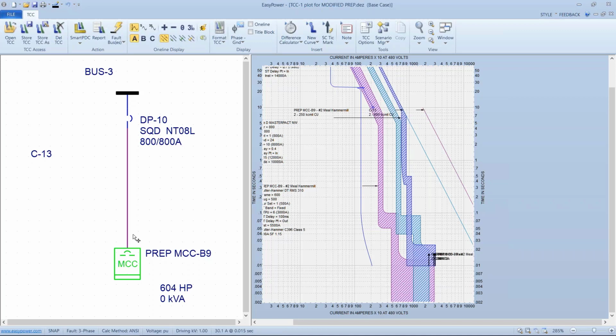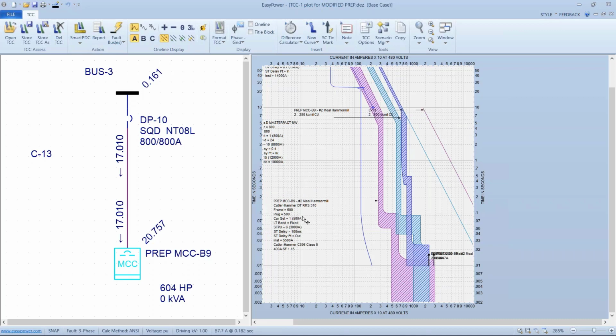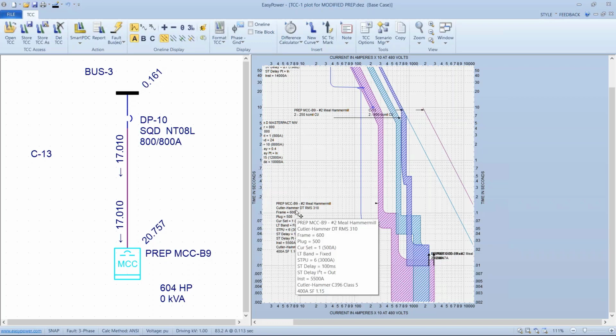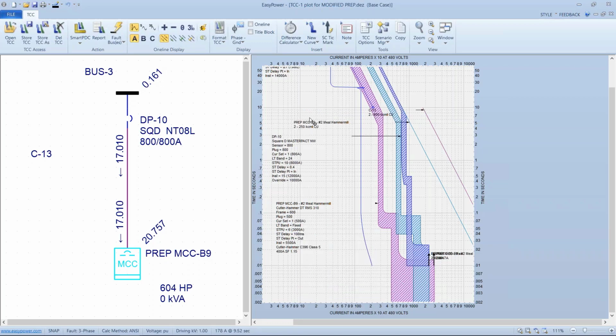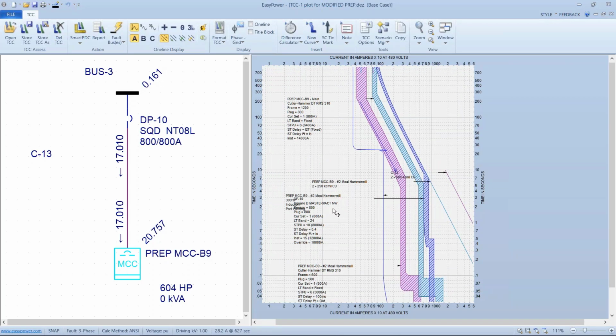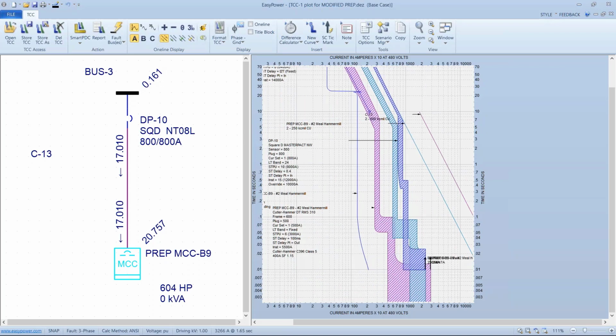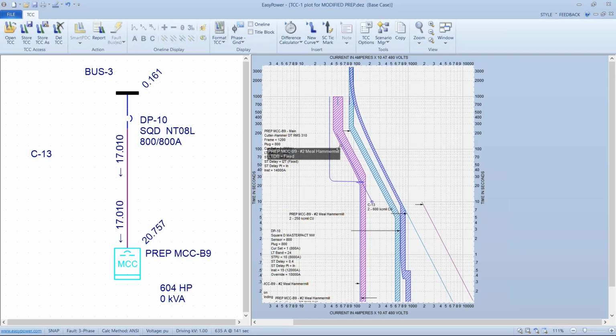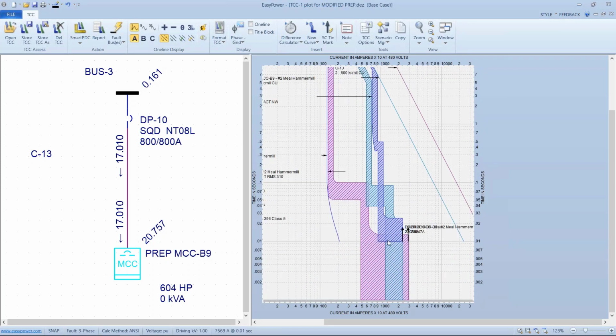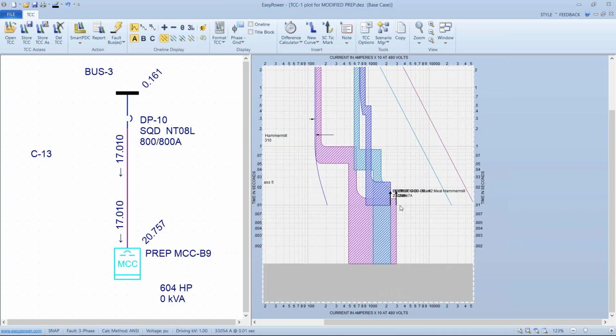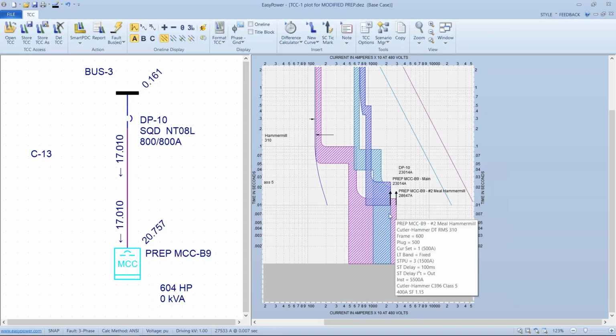And if we fault this downstream bus, so the procedure is fault the most distant bus, looking at current, what we're seeing here is the breaker in line with that large motor, and the large motor being plotted right here. So that's the starting curve. Ideally we want this breaker to be as close to the starting curve as we can get, and preferably inside of the damage curve. And then based upon where the fault is, we want that breaker to trip first. All right, so here's the maximum current that will occur in our breaker downstream for the motor.